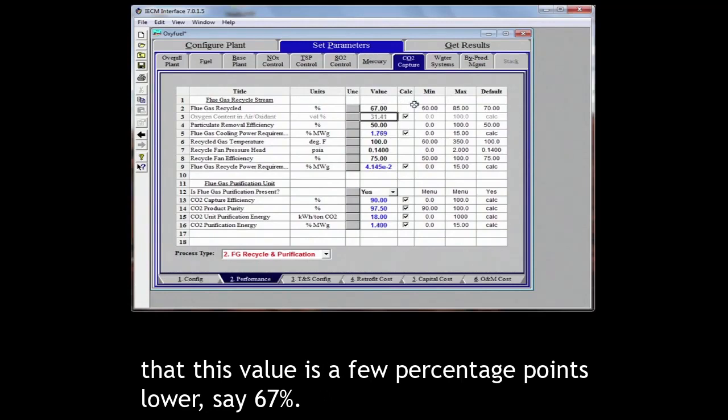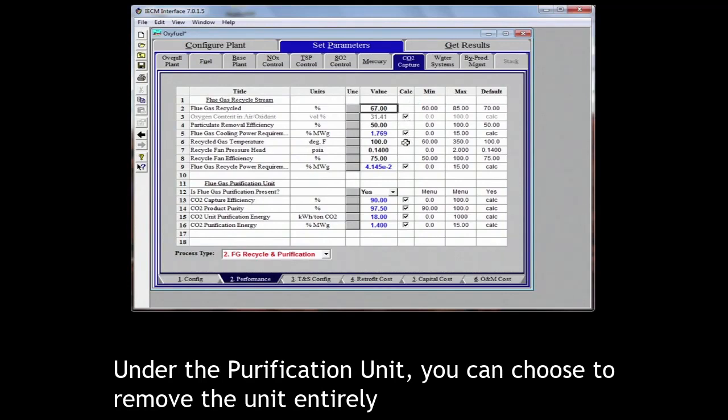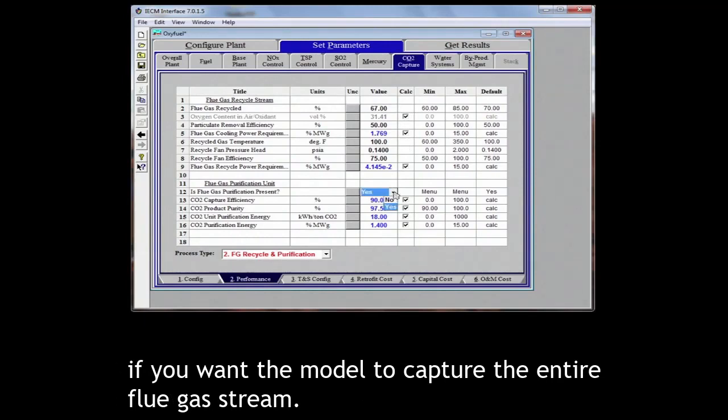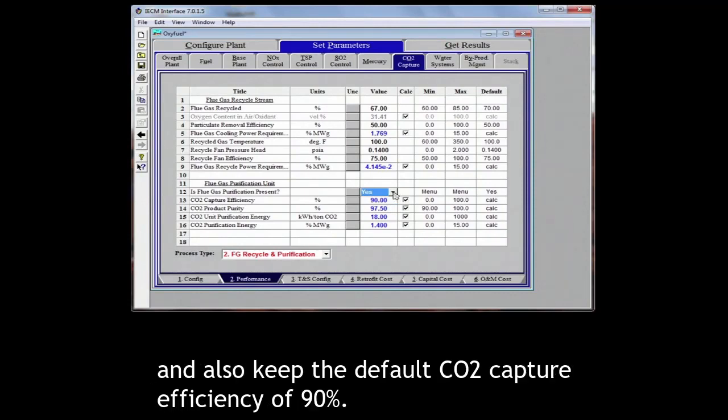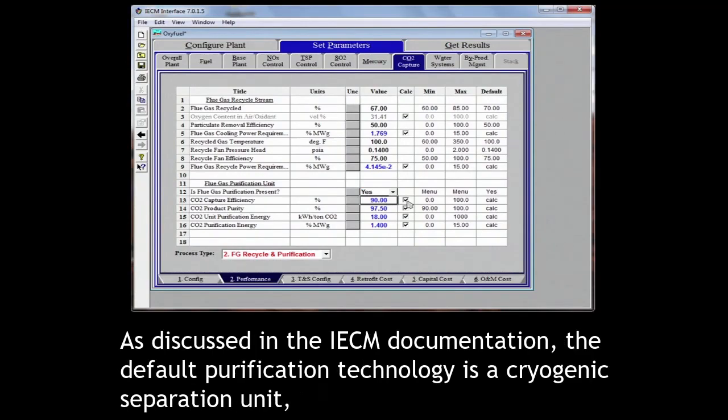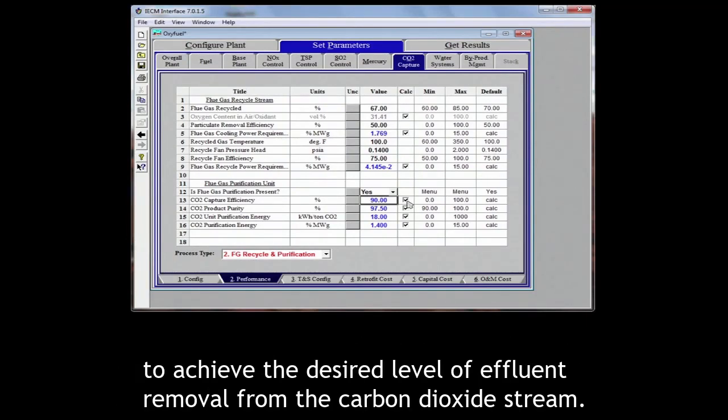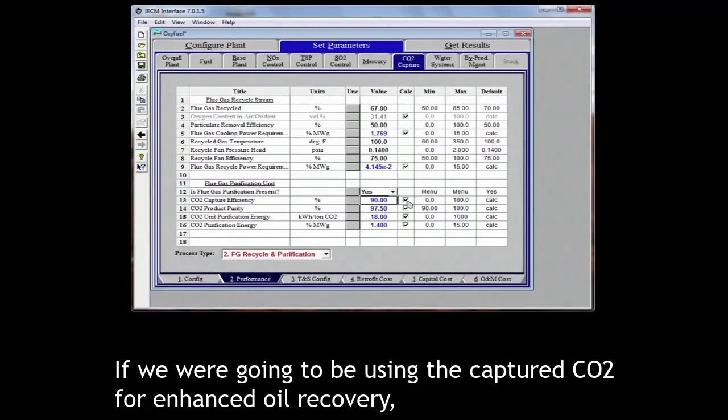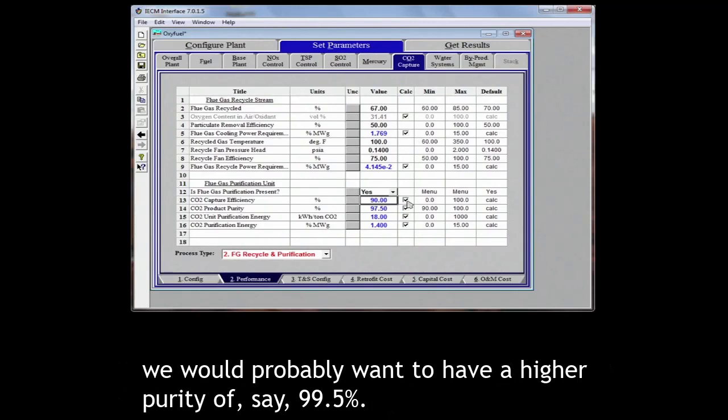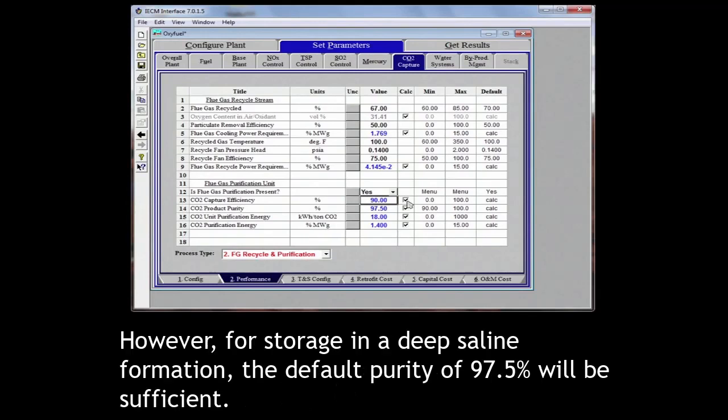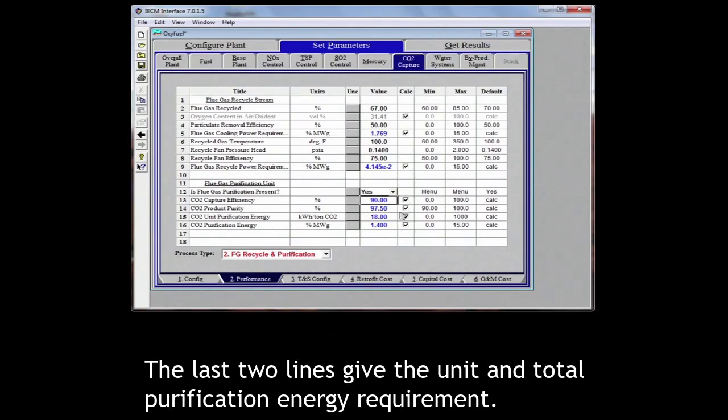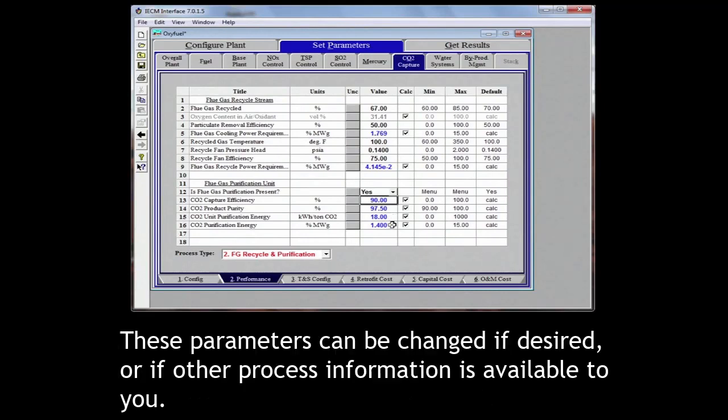Under the purification unit, you can choose to remove the unit entirely if you want the model to capture the entire flue gas stream. For this example, however, we will keep the purification unit and also keep the default CO2 capture efficiency of 90%. As discussed in the IECM documentation, the default purification technology is a cryogenic separation unit which uses a combination of knockout drums and/or distillation columns to achieve the desired level of effluent removal from the carbon dioxide stream. If we are going to be using the captured CO2 for enhanced oil recovery, we would probably want a higher purity of say 99.5%. However, for storage in a deep saline formation, the default purity of 97.5% will be sufficient. The last two lines give the unit and total purification energy requirement. These parameters can be changed if desired or if other process information is available to you.